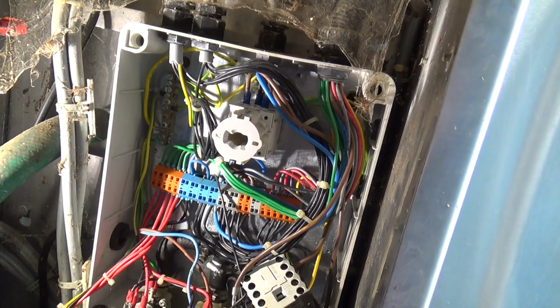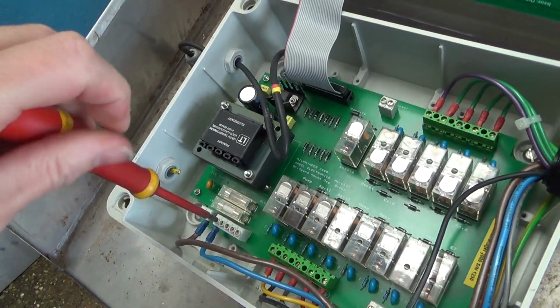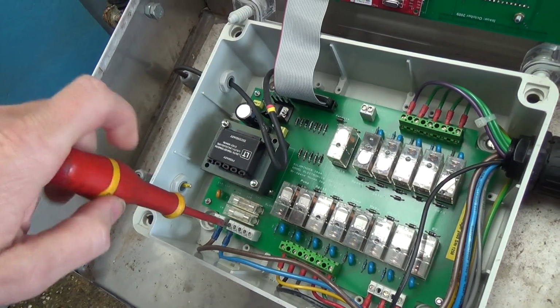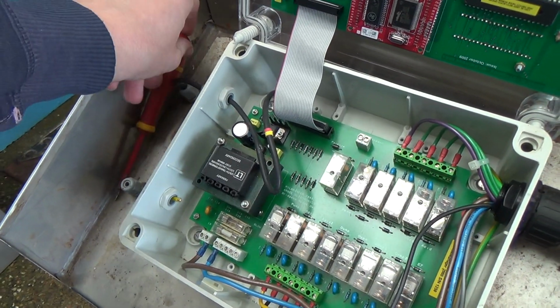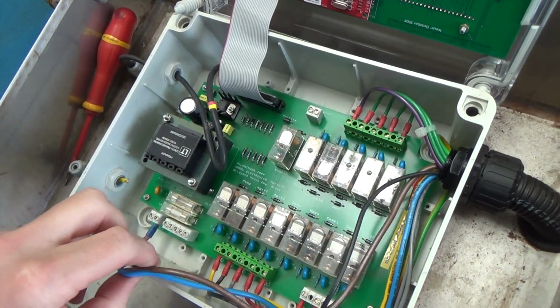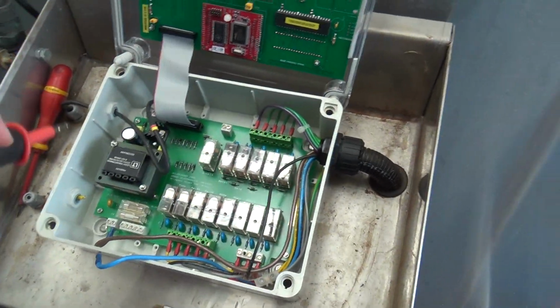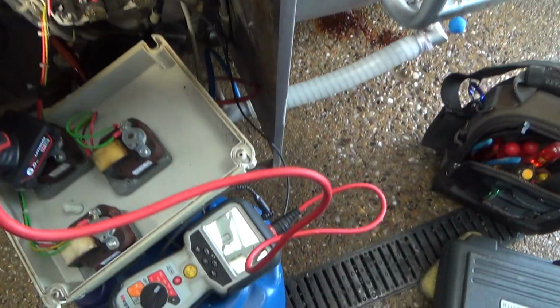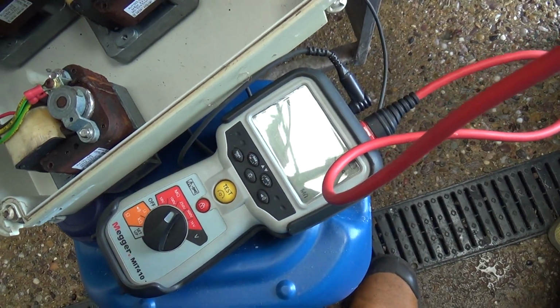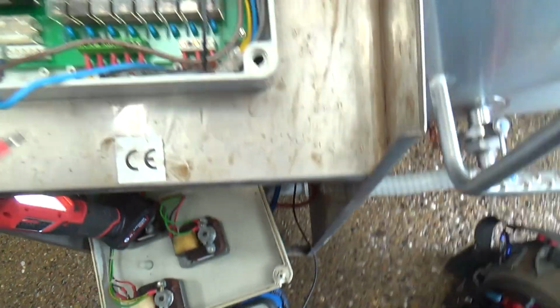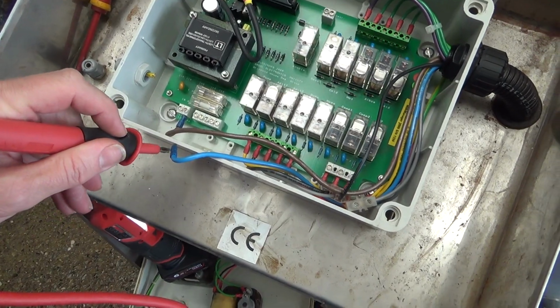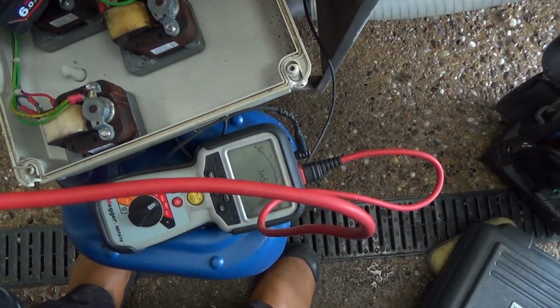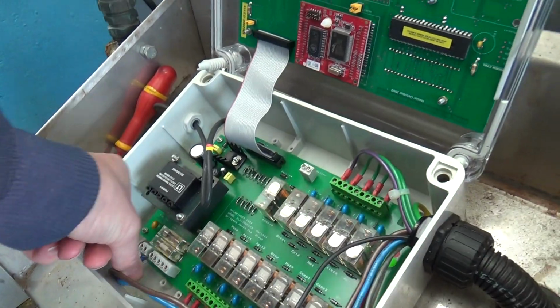So let's pop this neutral out of here. Generally all the neutrals for everything are connected, unless you've got a double pole contactor or something, a relay. All the neutrals are connected together. So if you get one thing faulty, it will go back up the neutrals and it'll make everything that's connected to that thing look faulty. There we go. So we've chased the fault into this box and then back out again because that should be shorted. Yeah, it's down the neutral. So we can pop that back in. We don't need to be in this box, I don't think.